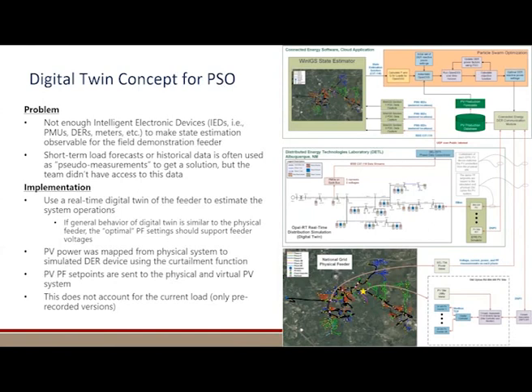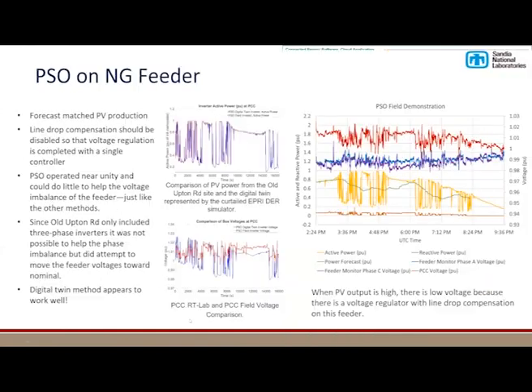We also don't really know any of the settings for the actual field in terms of tap changing transformer positions, or voltage regulation equipment, if it's on or off, cap banks, et cetera. So it's a kind of rough estimate, but it seemed to work pretty well for us. And here is an example run for that. There's a lot going on here, so I'll just point out a couple of things.